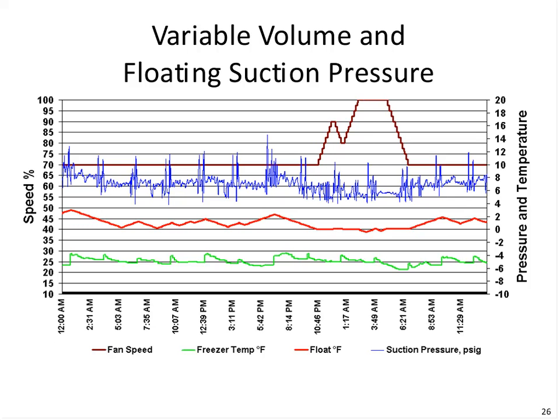And so this may be when a shipment arrived, the dock doors were opened, temperatures were going up. So notice at this point here, full fan speed, no floating of the suction, but then recovery occurred, temperature back down below the set point. So the fans go back to the lowest speed, and then notice here we start floating the suction pressure again.